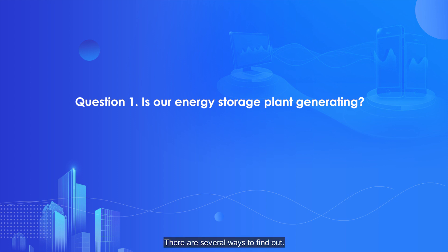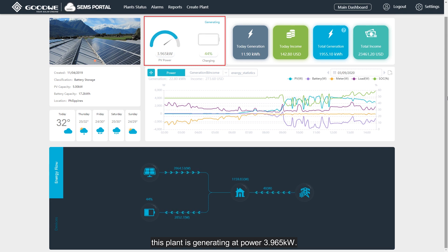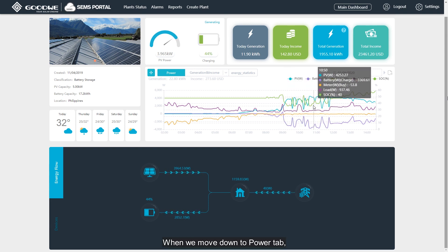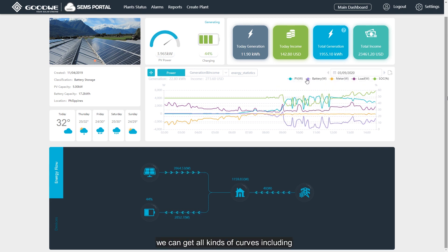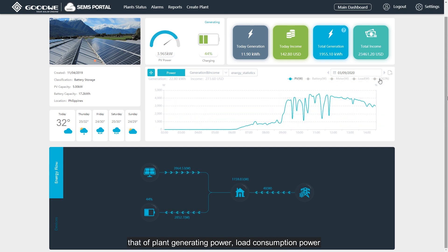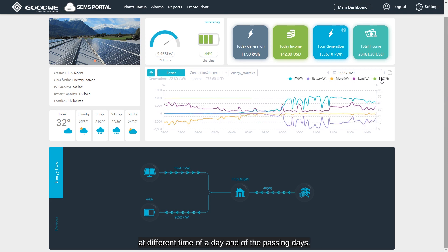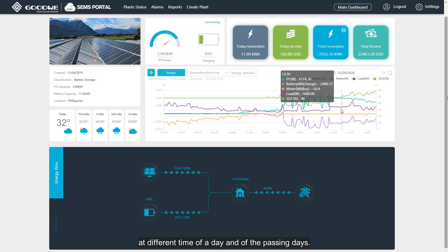There are several ways to find out. From the operation status tab, we know from the pointer that this plant is generating at a power of 3.965 kW, and the battery is charging but not full yet. When we move down to the power tab, we can get all kinds of curves including plant generating power, load consumption power, and battery charging or discharging power at different times of the day and of the passing days.